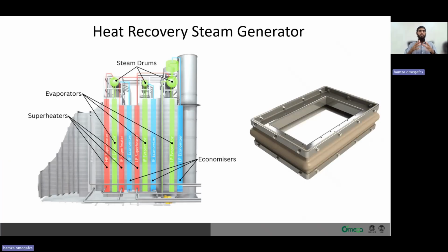So now we talk about the heat recovery steam generators that we mainly see in power plants, in combined cycles that we have studied. The heat recovery steam generator is a system that captures hot exhaust gases from sources like gas turbines and converts their thermal energy into useful steam. This steam can then be used to drive a steam turbine for electricity generation or for various industrial processes in a cogeneration system. Heat recovery steam generators significantly increase the overall energy efficiency and reduce the carbon footprint of power generation and industrial facilities. These consist of four major components: the economizer, the evaporator, the superheater, and the water preheater.